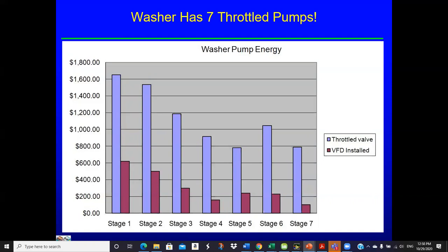So within 2 weeks, they had these VFDs installed and the valves open. So that's measured savings on these pumps. That's done by Schneider, and we put the actual measured savings in our report. That's pretty good. That's the only time that's ever happened, and probably the only time it ever will happen.